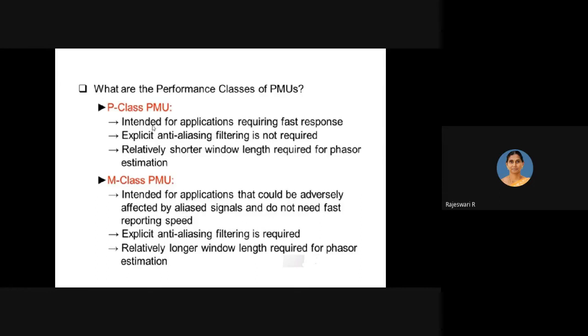P class, requiring faster response, doesn't bother about high frequency content. Its operation relies on a very shorter window length of captured data from the power network, meaning fewer samples in a cycle. The window length decides the accuracy of measurement, so here the number of samples acquired in a cycle or window is less.